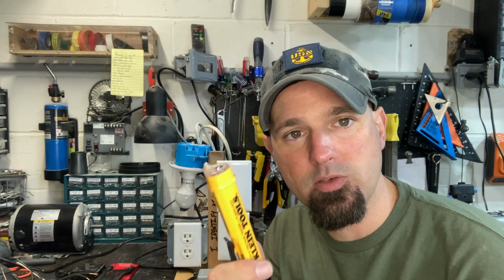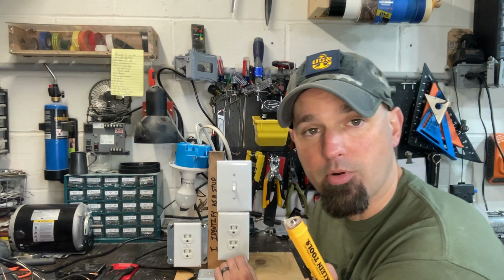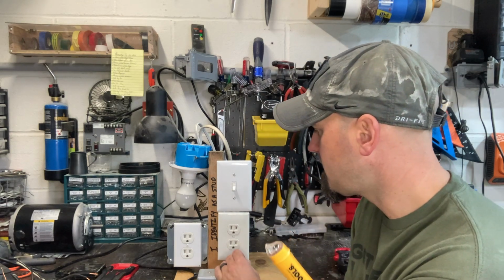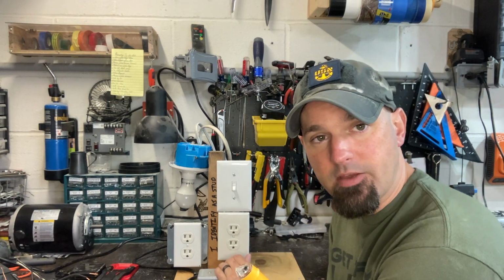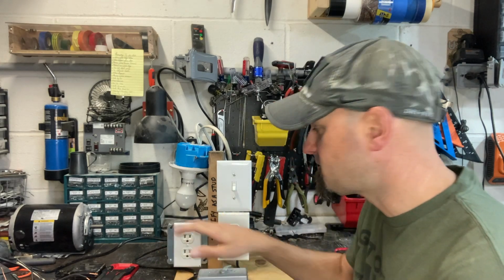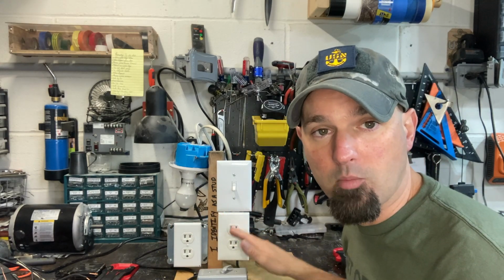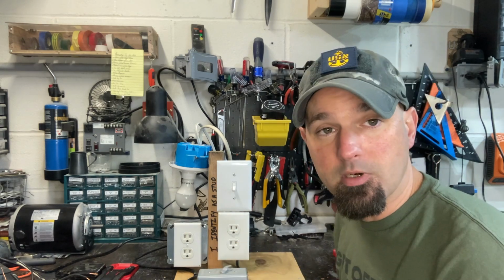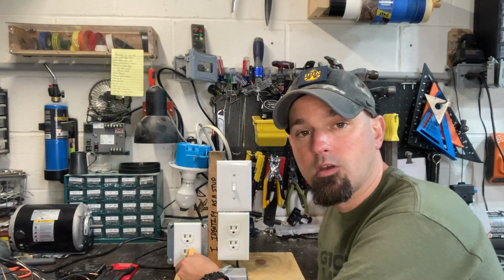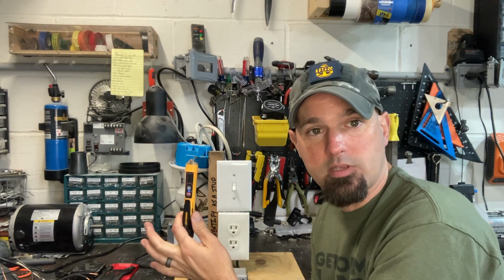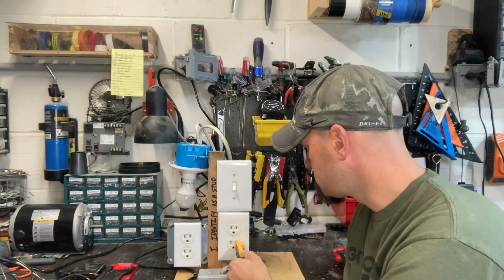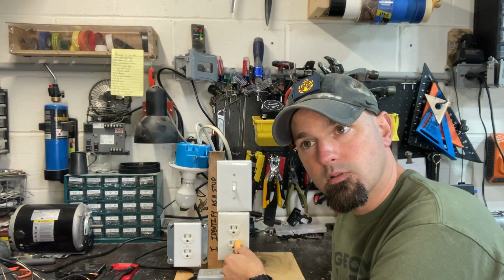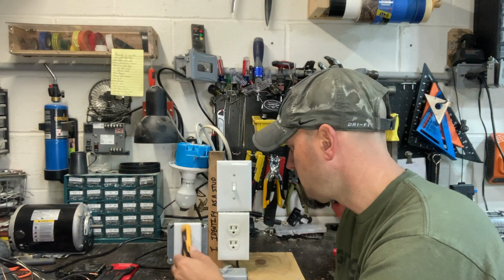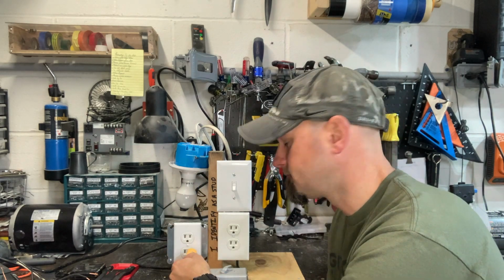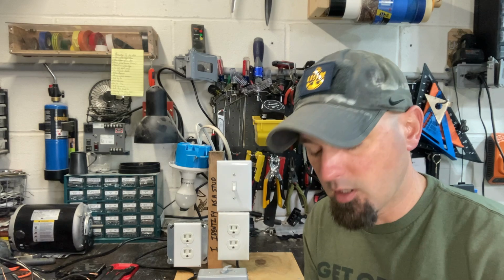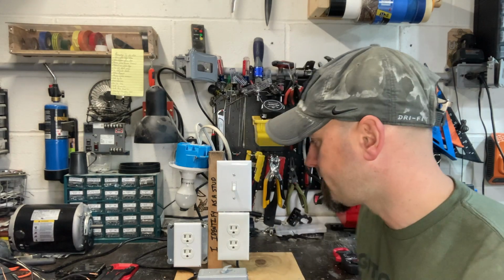Now let's go back to what we were doing before. I still have my circuit breaker in the off position, and I want to test live because I know this is live. Say this is my kitchen and this is my bedroom, and I'm working in the bedroom. First I'm going to come over here, and okay, that's a live circuit. Now I'm going to come over to this one. Nothing, right? Now I'm going to come back over to my live circuit. Okay, see, live, dead, live. I just made sure that it was exactly off.